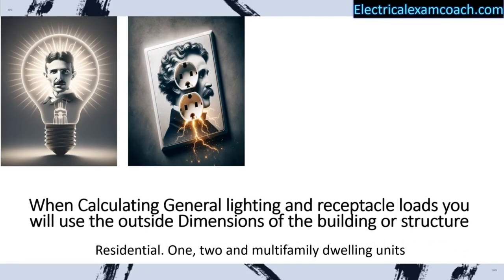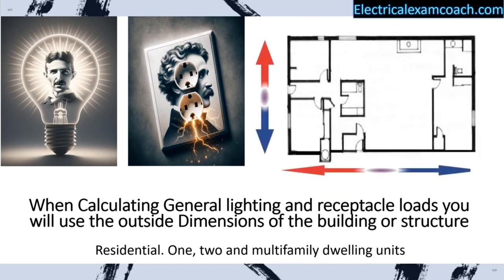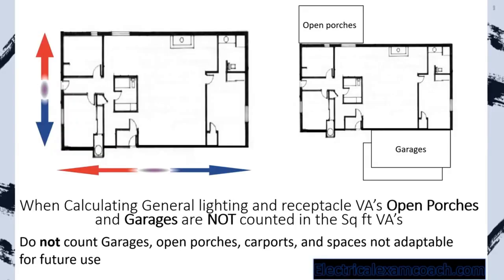When calculating our general lighting and receptacle loads, we will use the outside dimensions of the building or structure — we measure from the outside in both directions. Open porches and garages are not counted in our general square foot VAs. We do not count garages, open porches, carports, and spaces that are not adaptable for future use.